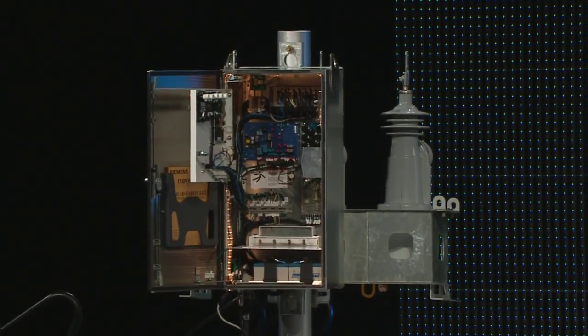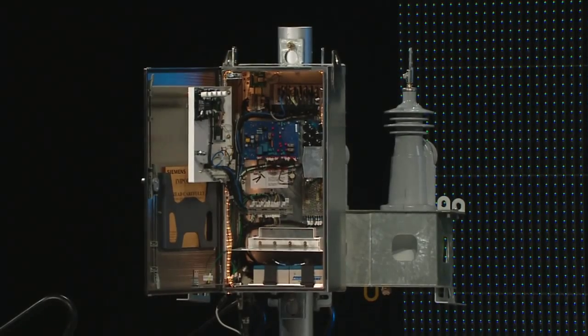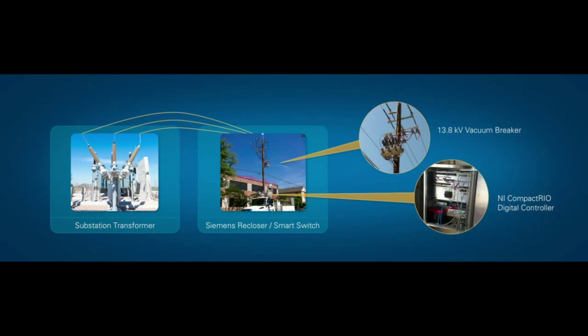Essentially it monitors the flow of power on a pole, and if there's a problem it'll alert the utility so they can shut down the power. At the heart of that smart switch is a CompactRIO that's monitoring the flow of three-phase AC power, controlling the vacuum breaker that can shut off the 13.8 kilovolts, and streaming that back to the utility over a redundant wireless grid. In the future, when there's a fault, it'll use adaptive pattern matching to identify what the fault is and provide the utility with more information.